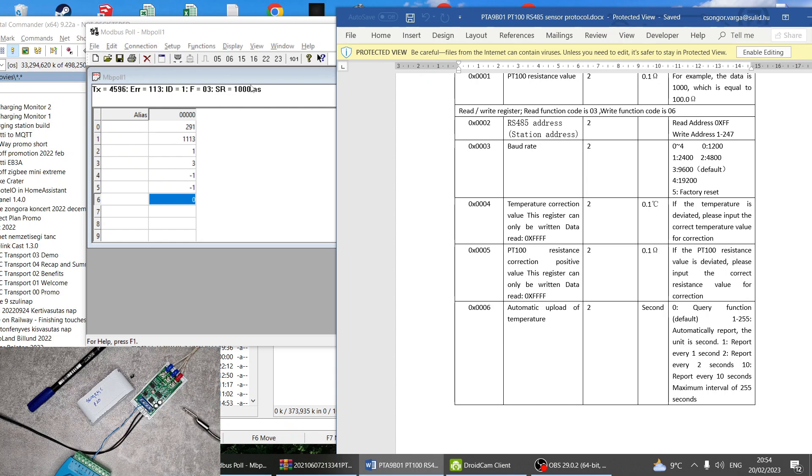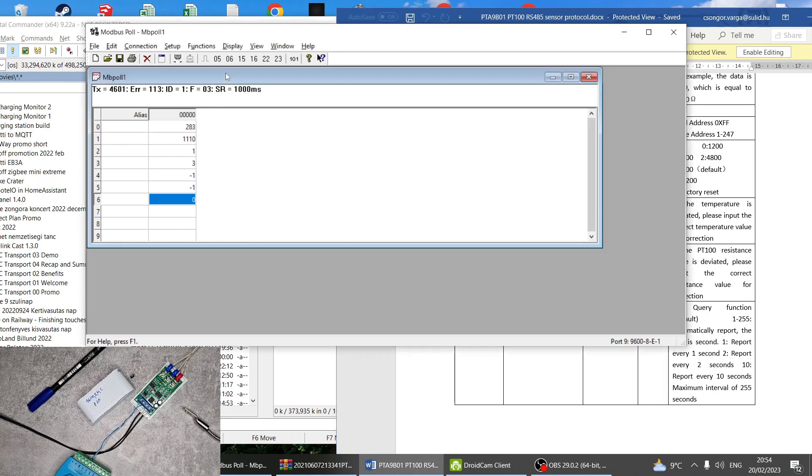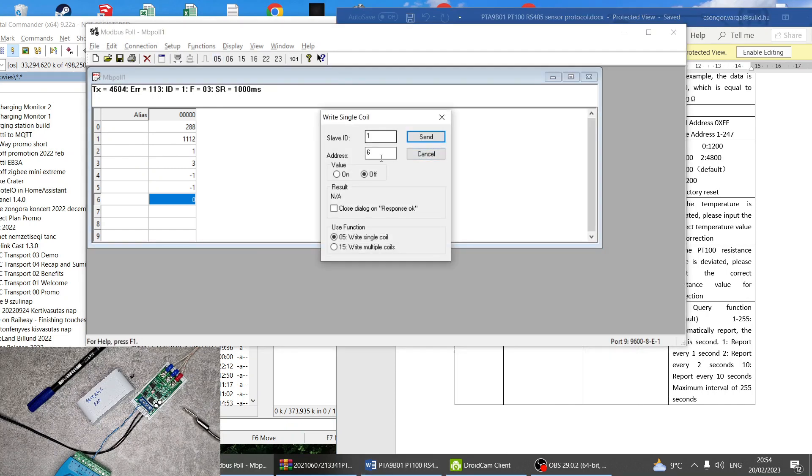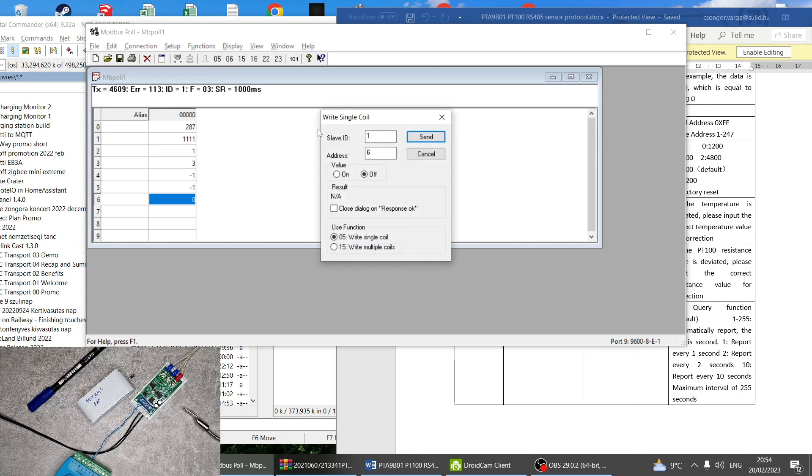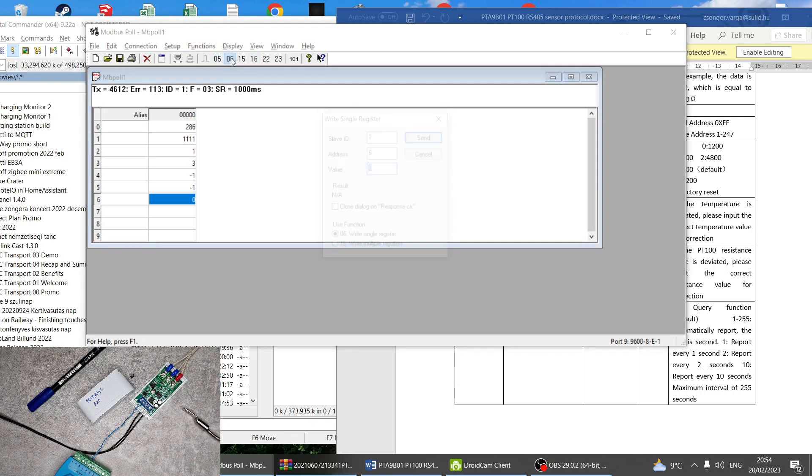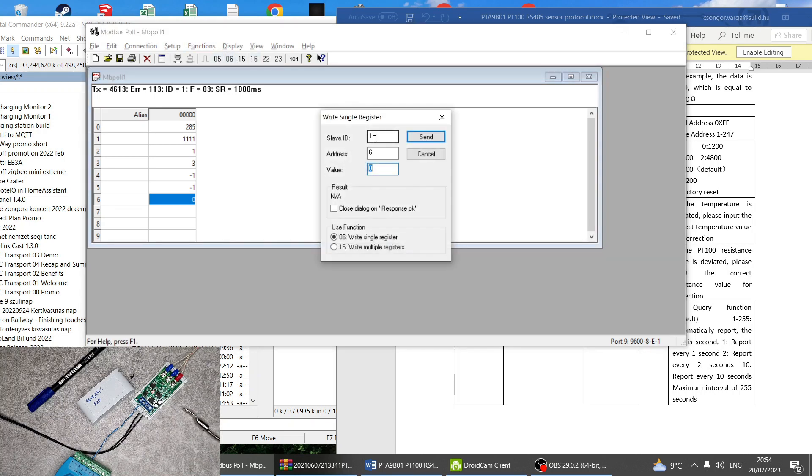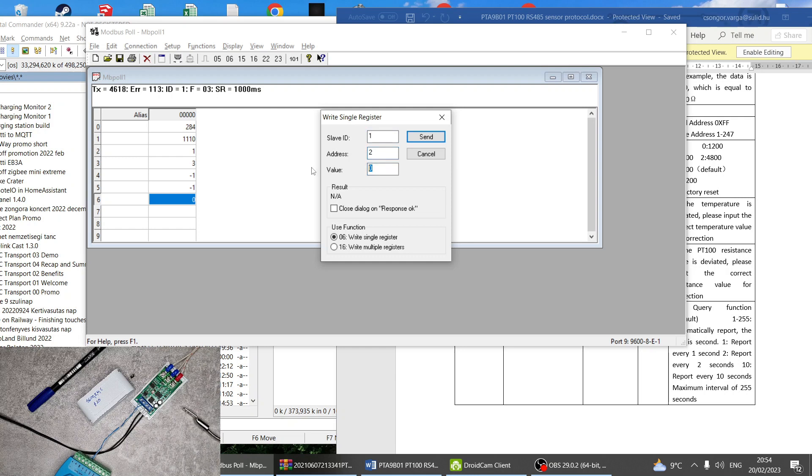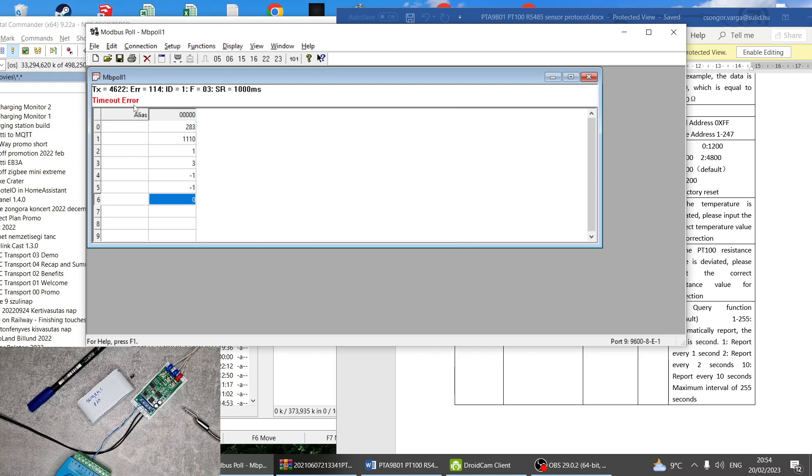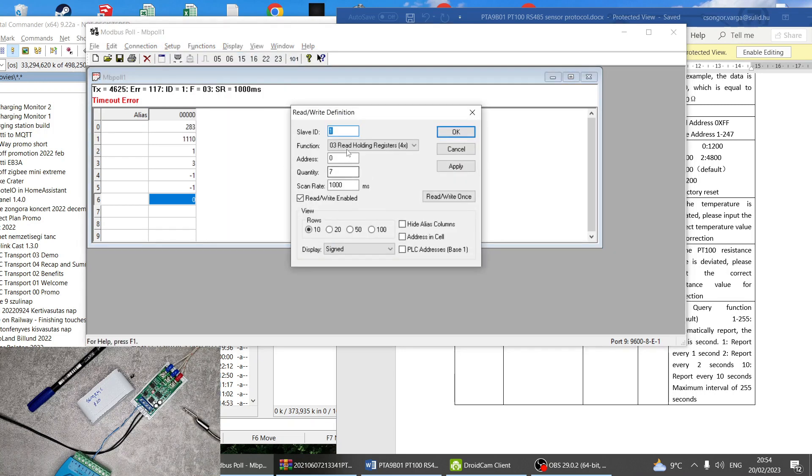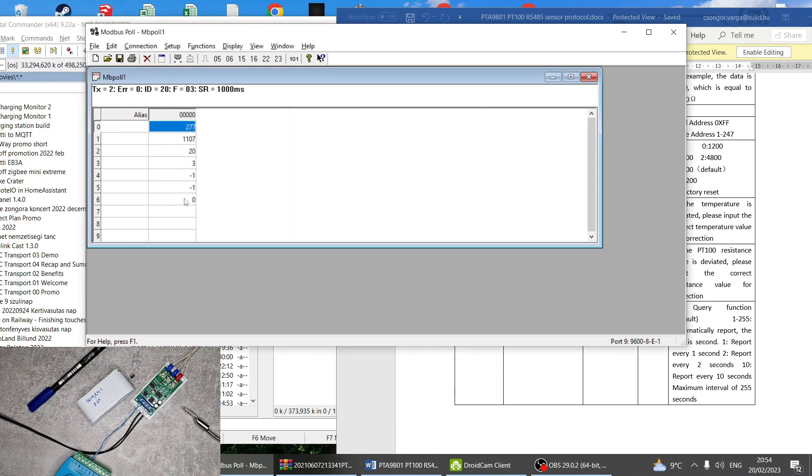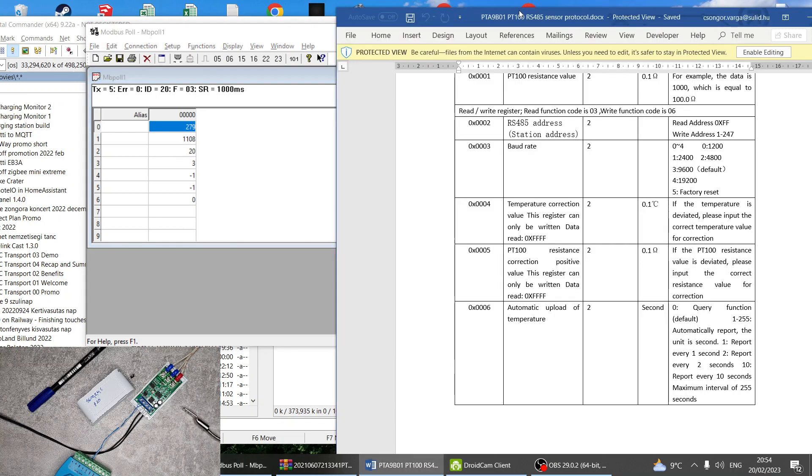For example here I'm reading every 1000 milliseconds. Let's change the address, so at the moment we're on slave 1 and this is address 2. I want to change the station ID or the slave ID to 20. Now response is okay, so this is obviously no longer working because we just changed the slave ID. But if I change that and then we set, now we can see that now we're reading the device on the new address. So it's that easy to change it.